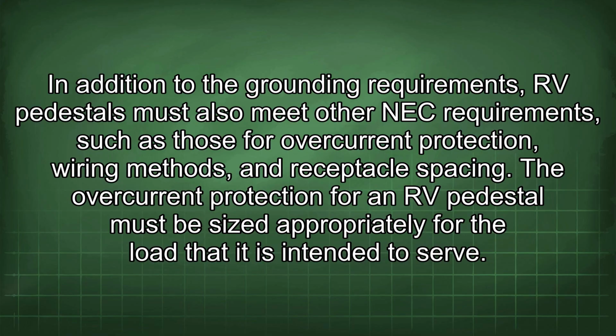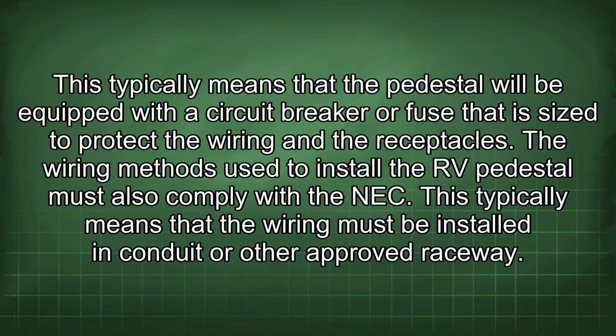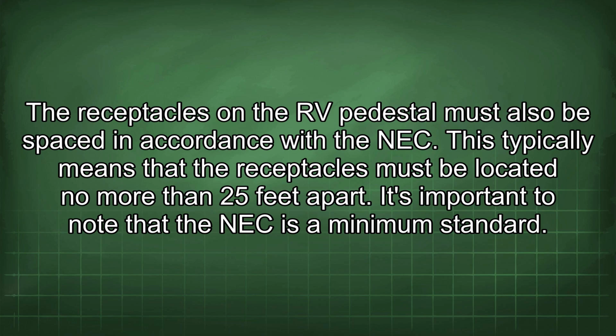The overcurrent protection for an RV pedestal must be sized appropriately for the load that it is intended to serve. This typically means that the pedestal will be equipped with a circuit breaker or fuse that is sized to protect the wiring and the receptacles. The wiring methods used to install the RV pedestal must also comply with the NEC. This typically means that the wiring must be installed in conduit or other approved raceway. The receptacles on the RV pedestal must also be spaced in accordance with the NEC. This typically means that the receptacles must be located no more than 25 feet apart.